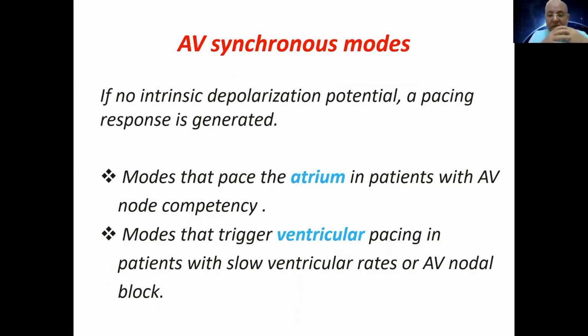We have two main modes: synchronous mode and asynchronous mode. Synchronous mode: if there is no intrinsic activity, intrinsic depolarization in the chamber, whatever the chamber, atrium or ventricle, a pacing response will be generated. If there is no intrinsic activity, there is pacing. If intrinsic activity is present, there is no pacing. If the AV node is okay, with no dysfunction, it can sense and pace the atrium. If there is AV node block, we can sense the atrium and pace the ventricle.